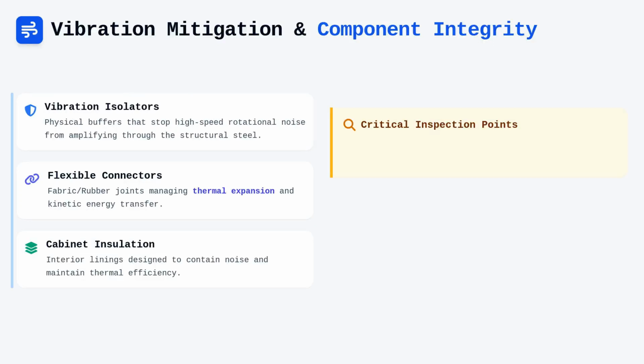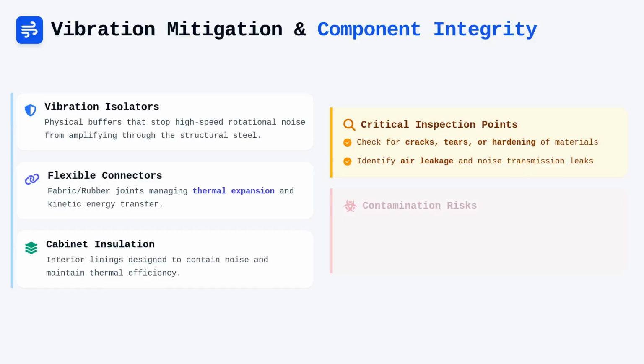When inspecting these components, it is necessary to check for cracks, tears, or hardening of the flexible material, as any breach here results in air leakage and noise transmission. Furthermore, the insulation lining the interior of the cabinet must be inspected for signs of shedding, delamination, or microbial growth, all of which can introduce contaminants into the airstream.